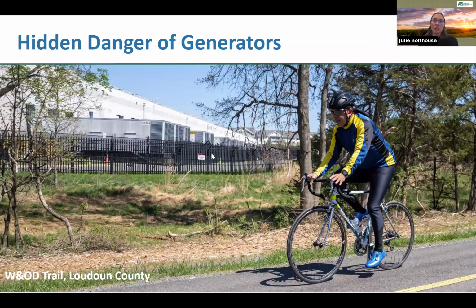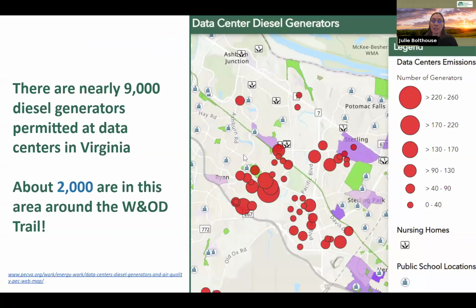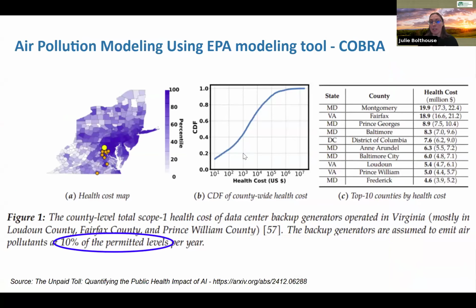Then there's the hidden danger of all those generators. There are so many on site that the cumulative impacts of all these minor permits, which had no public review, are becoming very pronounced—2,000 just in that area. That picture of the Washington and Old Dominion Trail is the green line on this map, and we have 2,000 generators within about a 2 mile corridor that could all kick on during an outage event, or increasingly are being proposed for use in things like demand response or planned outage events.